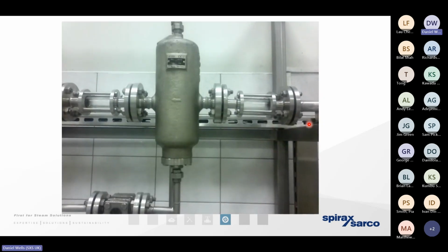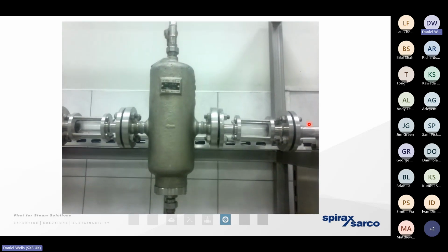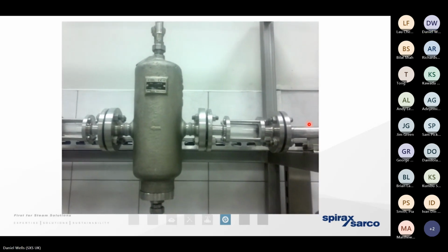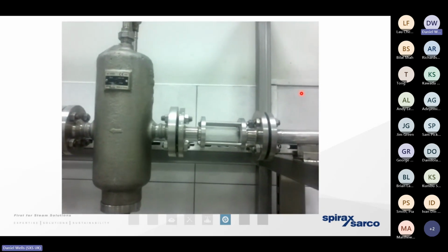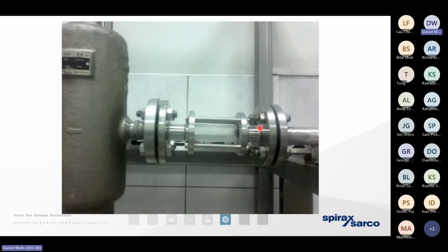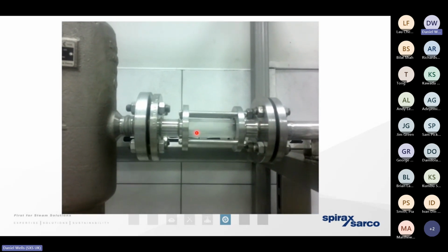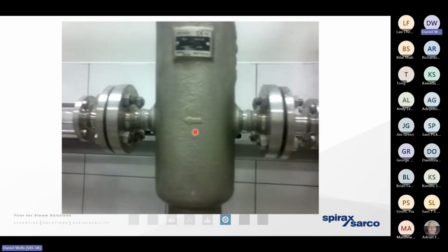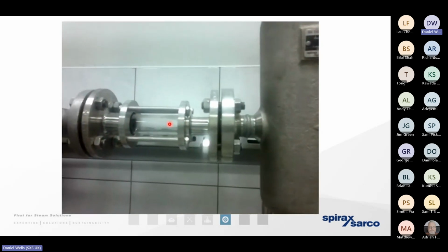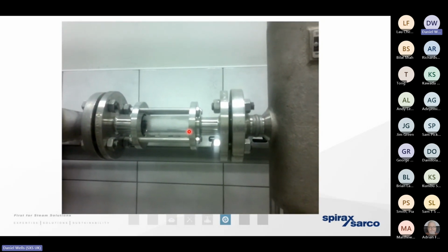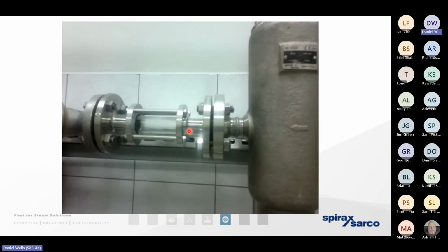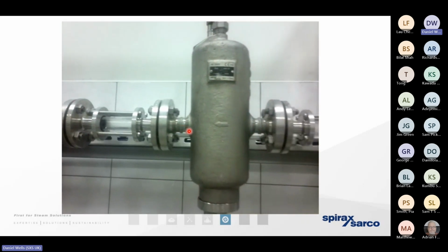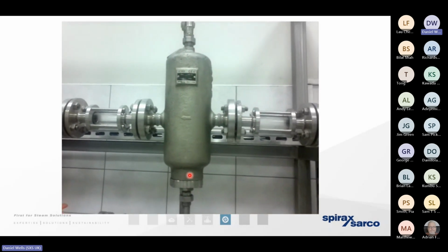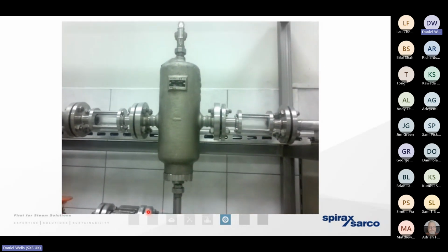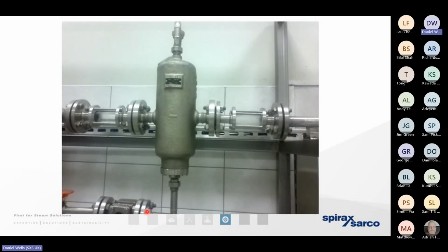So this is an example of a steam separator in action. You'll see the steam coming in over at the right-hand side of the screen. You'll see the moisture that the steam is carrying in the bottom of the sight glass. And by referring to the steam that is exiting the separator, you can appreciate the extent to which we've now dried that steam. You can appreciate the massive condensate that is being taken away from the steam trap at the bottom of the separator.